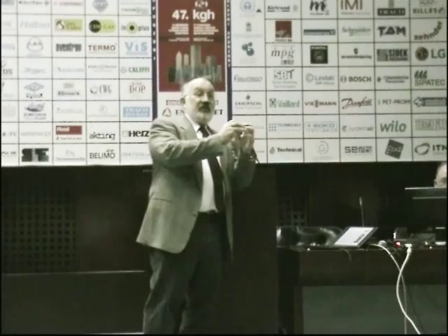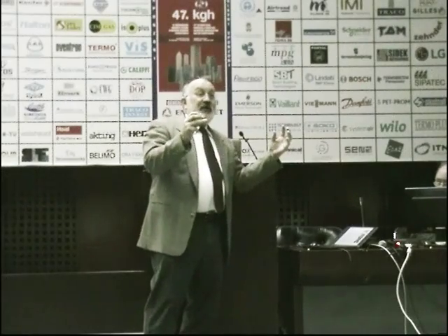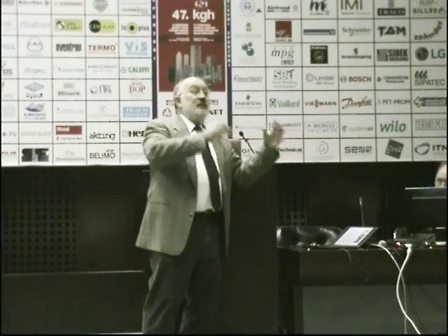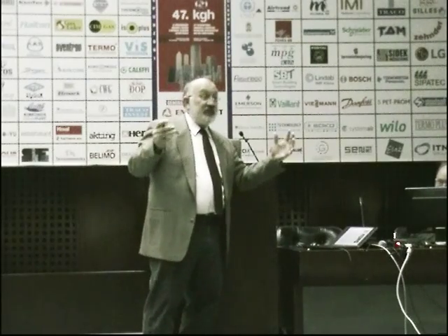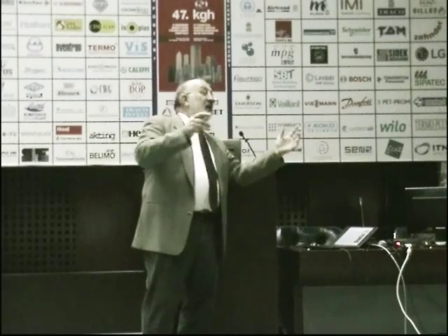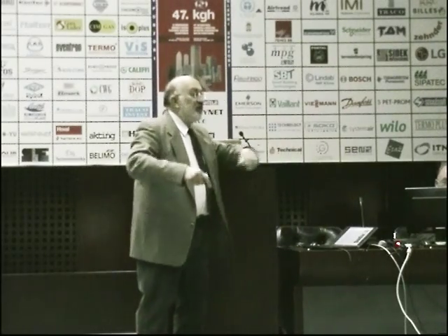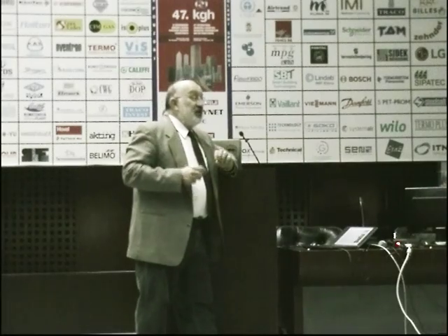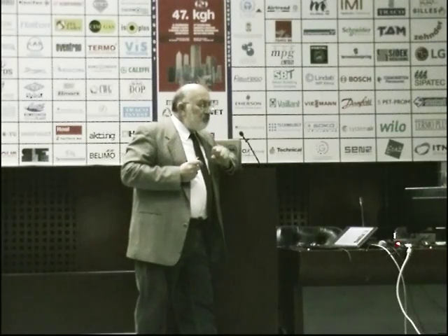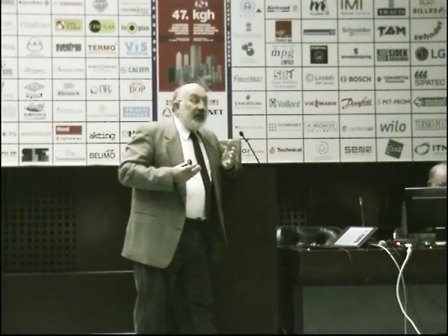Then the problem in visualization is you always have a lot of oil inside. You can have a discharge and you will see, there will be a transparent discharge too. And in the end, we made a transparent compressor discharge chamber of the compressor. So we can now see, and I will show you something about valves, but this is a separate presentation about flow of oil in the discharge chamber of the compressor. Then we had to develop a totally new technique.